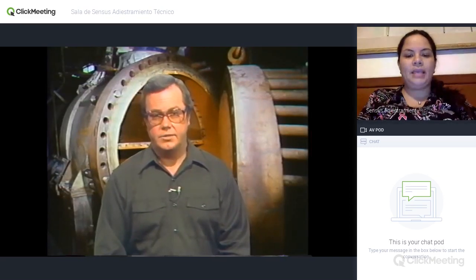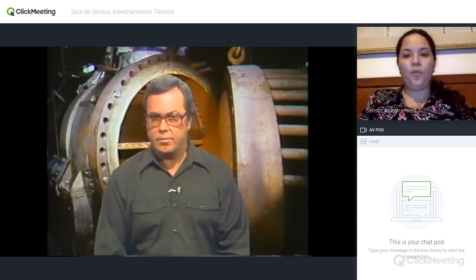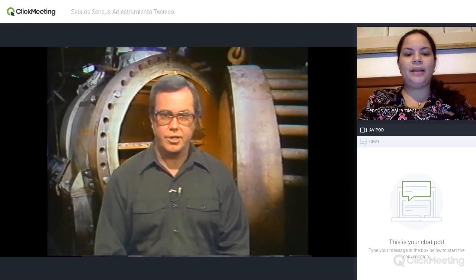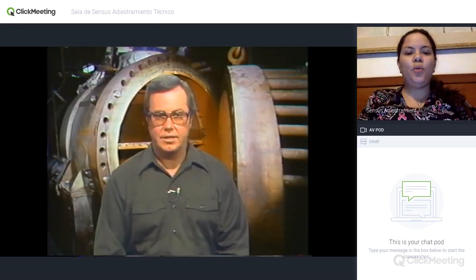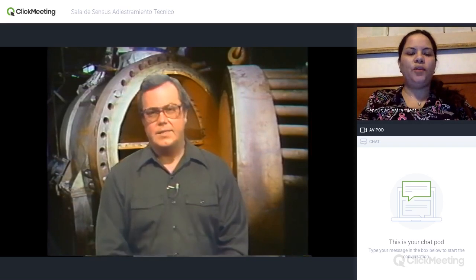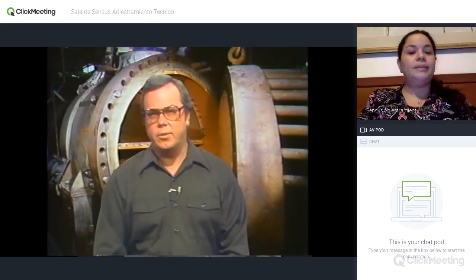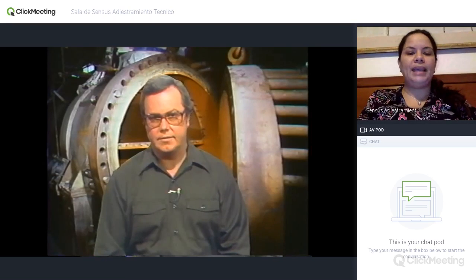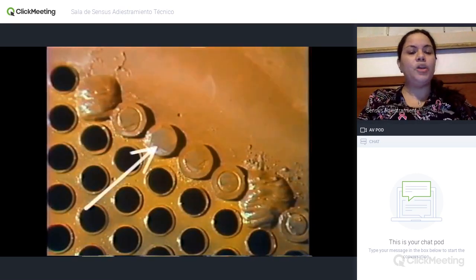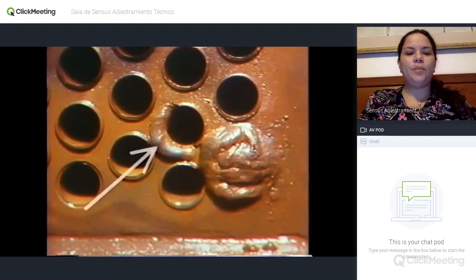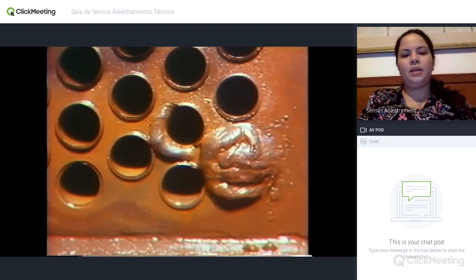Now, generally, you plug a leaking tube at each end to keep fluid from going through. Normally, you don't try to stop the leak itself. Later on, we'll be seeing in detail how plugging is done. Sometimes you may find a leak around where a tube goes through the tube sheet. You might have to plug the tube, or you may be able to weld the end of the tube to the tube sheet. It's possible you may have to do both.